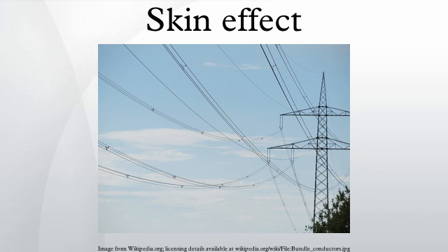In Engineering Electromagnetics, Hayt points out that in a power station a bus bar for alternating current at 60 Hz with a radius larger than 1/3 of an inch is a waste of copper, and in practice bus bars for heavy AC current are rarely more than half an inch thick except for mechanical reasons.